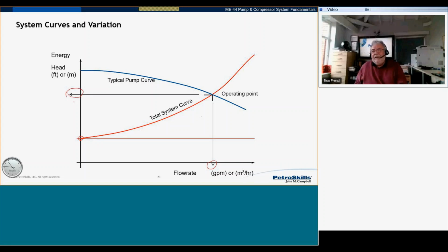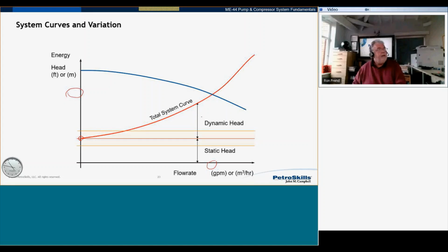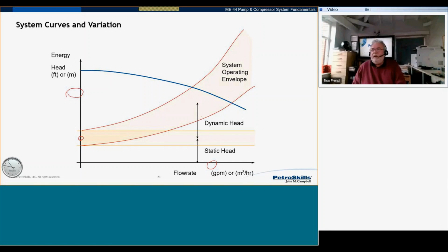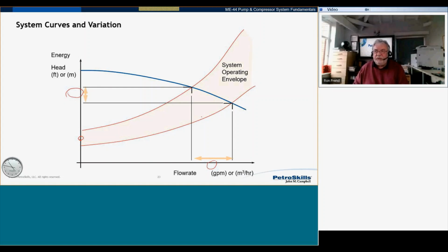But what if those tank levels don't stay the same? What if those tank levels change? What if the pressure in the suction tank or the pressure in the discharge tank start to change? What if, and heaven forbid, your control valve starts to operate and you get different friction losses? Good grief, what are you going to do? What you should do is think about those changes. Think about the changes in the static head, but also think about the changes in the friction head. What you end up with is a system operating envelope. This is the information you need to send to the vendors. This is what I would call doing a sensitivity analysis. So you could be operating in that flow, or that flow, and either of those two heads, or anywhere in between, depending on the operation at that particular time.